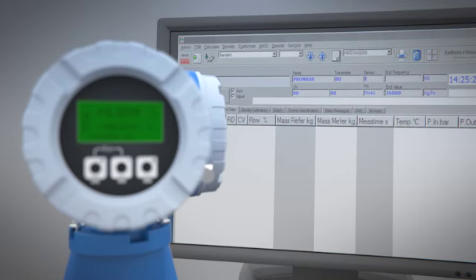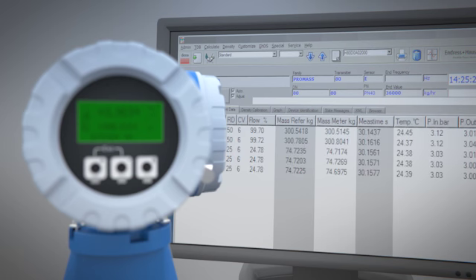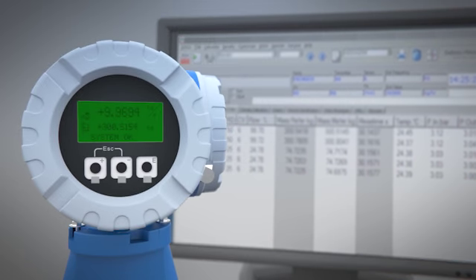The last step of the calibration process is to calculate the reference mass flow based on the data collected, the measured time and mass. This reference value, determined with the scale, is compared to the value measured by the device under test to determine its deviation. This comparison makes it possible to correct tiny discrepancies by adjusting the device.